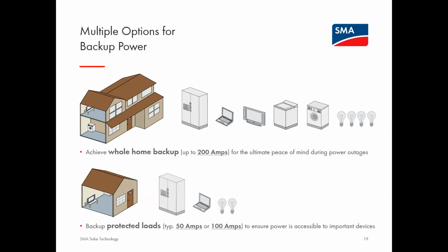In addition, a second option you have when designing your system is to install a second load panel, a sub panel if you will, and put only the circuits on that sub panel that you intend to back up. So it's a protected load panel. Typically, this would be somewhere in the order of 50 or 100 amps, and you're picking and choosing which loads in the home, working with the homeowner, to choose what should be powered during a grid failure.